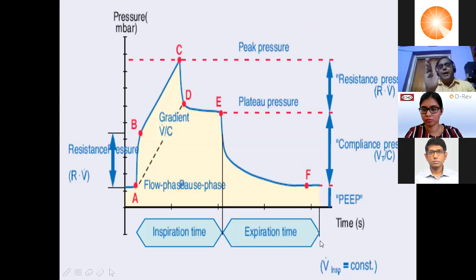Now my I time has stopped and my T pause has started. So as my T pause starts, what is happening to my lung? My lung is still expanded, but there is no flow. But what happens to my pressure? My pressure suddenly drops to a certain extent and then stays there till the end of the T pause. And as my T pause finishes and I cycle to expiration, then my pressure goes down to the level of PEEP. So in VC, rather than having two pressures, we have three pressures. We have one peak pressure, one PEEP, but we have one more secondary point here, and this pressure is called the plateau pressure.